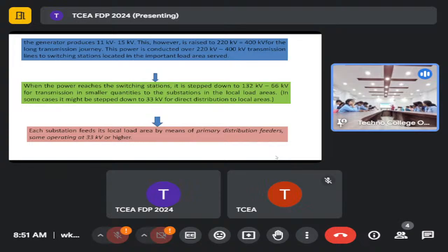The generator produces 11 kV to 15 kV. This, however, is raised to 220 kV, 400 kV for long transmission. This power is conducted over 220 kV, 400 kV transmission lines to switching stations located in important load areas. When the power reaches the switching station, it is stepped down to 132 kV to 66 kV for transmitting smaller quantities to substations. Can you say this is a substation or a switching station?